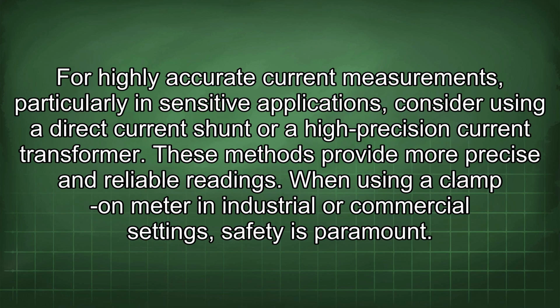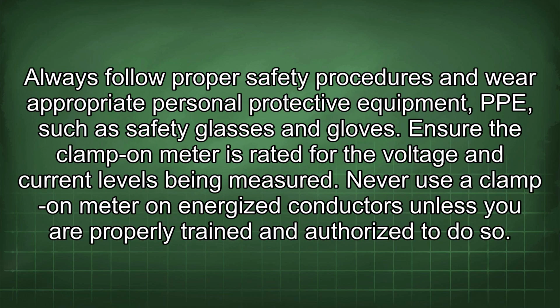For highly accurate current measurements, particularly in sensitive applications, consider using a direct current shunt or a high-precision current transformer. These methods provide more precise and reliable readings. When using a clamp-on meter in industrial or commercial settings, safety is paramount. Always follow proper safety procedures and wear appropriate personal protective equipment, PPE, such as safety glasses and gloves. Ensure the clamp-on meter is rated for the voltage and current levels being measured.